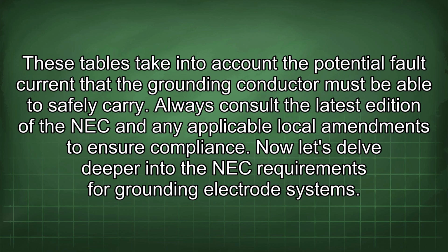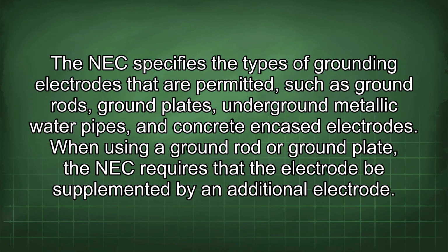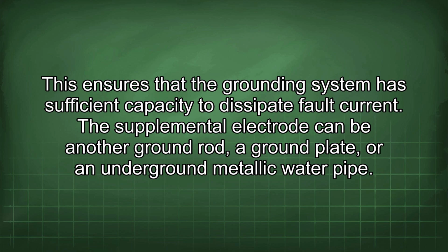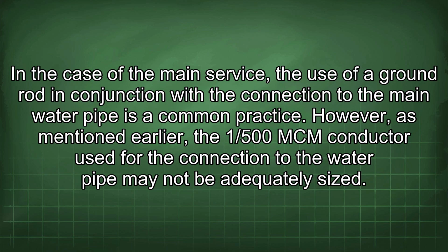Now let's delve deeper into the NEC requirements for grounding electrode systems. The NEC specifies the types of grounding electrodes that are permitted, such as ground rods, ground plates, underground metallic water pipes, and concrete encased electrodes. When using a ground rod or ground plate, the NEC requires that the electrode be supplemented by an additional electrode. This ensures that the grounding system has sufficient capacity to dissipate fault current. The supplemental electrode can be another ground rod, a ground plate, or an underground metallic water pipe. In the case of the main service, the use of a ground rod in conjunction with the connection to the main water pipe is a common practice.